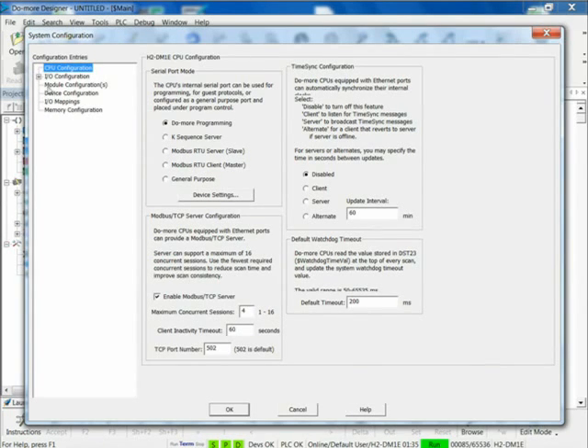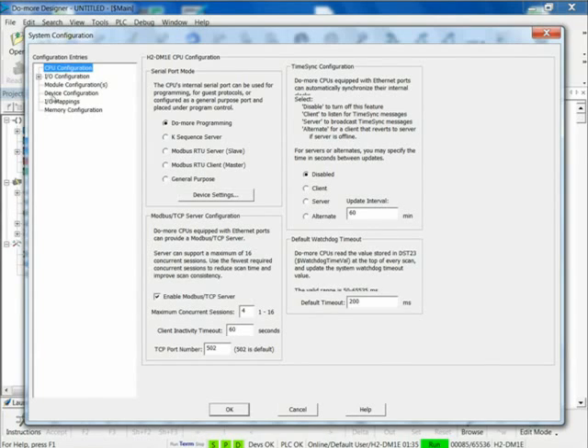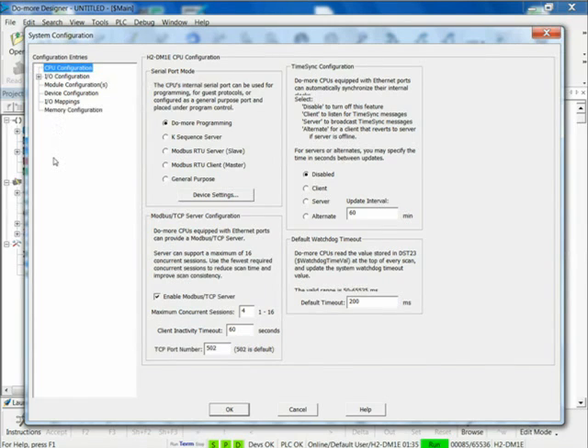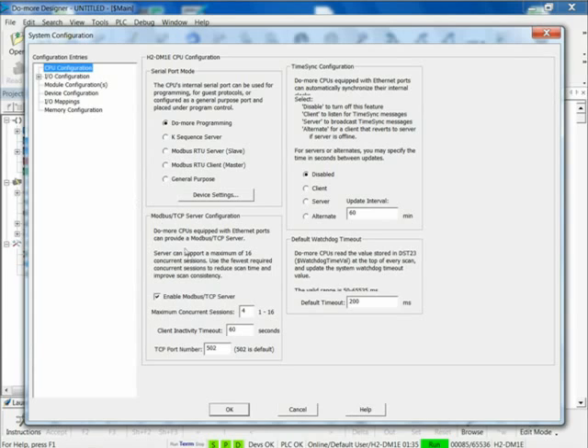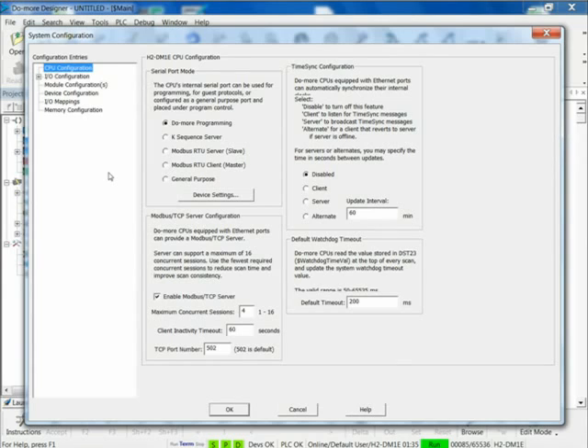Then what's dependent upon that is the modules that you have in your I/O configuration. Then below that is Device Configuration, I/O Mappings, and Memory Configuration. Just let's look at the CPU Configuration on the screen. That's where I go if I want to adjust the serial port settings or the Modbus TCP server settings, and set the time, set the watchdog. That's all under the CPU Configuration. All of this is under one menu called System Configuration, correct? Yes.